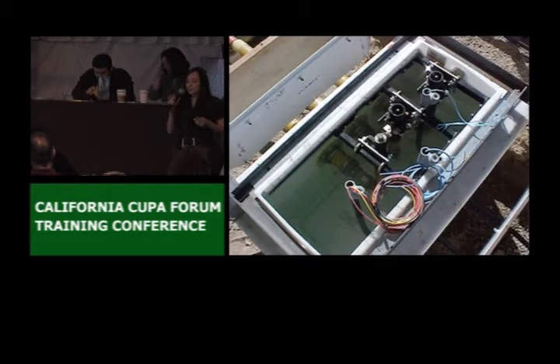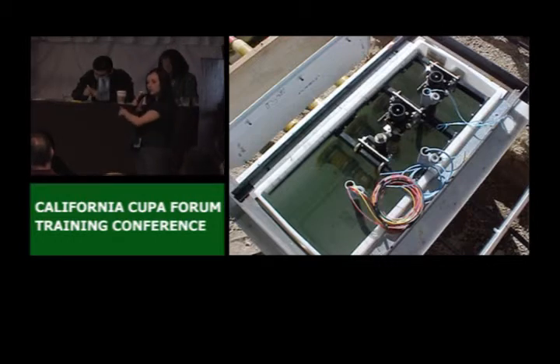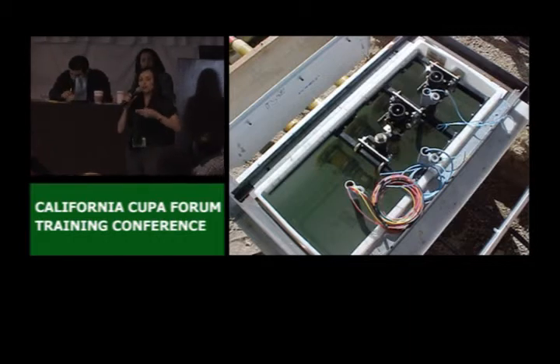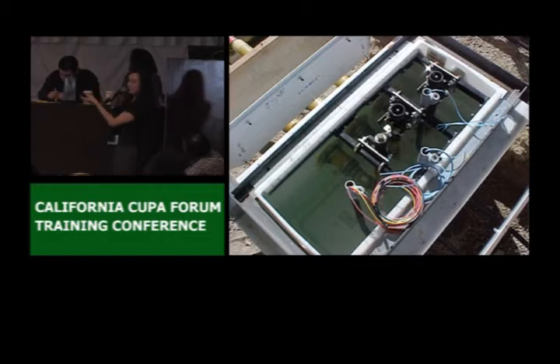Now, do we test those? Well, they have to be tested as well every year. Now, we cannot do a visual hydrostatic test. Why? Because we cannot observe around the under dispenser containment, right? So we have to do the one with the instruments. Now, if it's with instruments, it has to be done by the technician. And we have to make sure that whoever is doing the testing is certified to do the test.